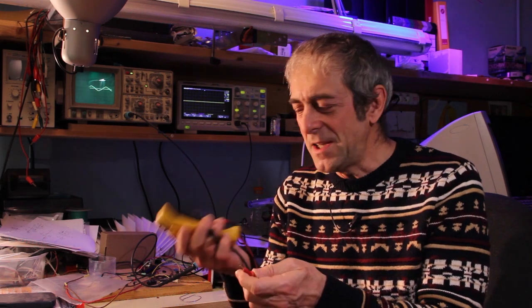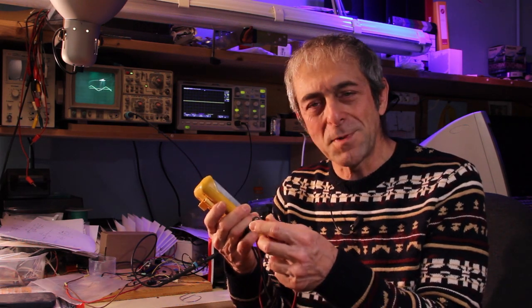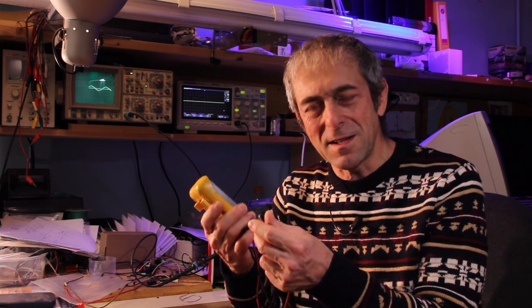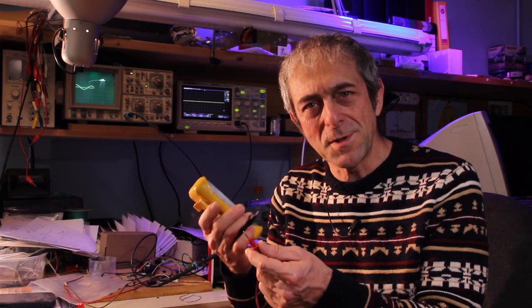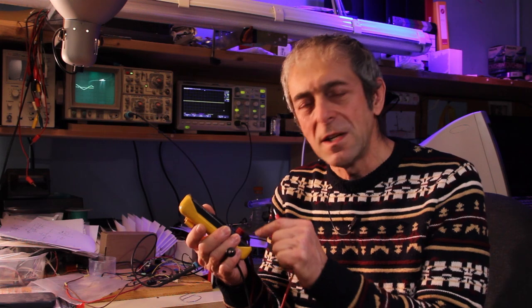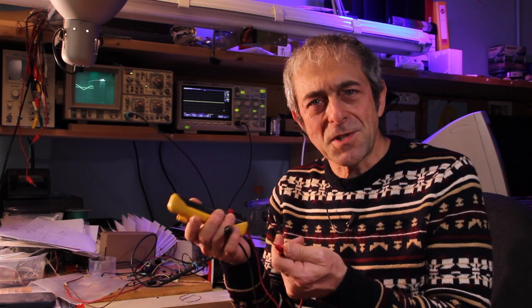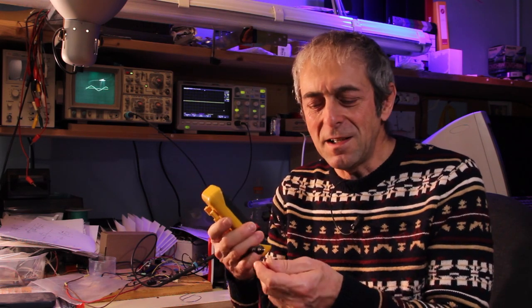Consider that in the continuity test, as you can see here with this instrument, when I touch the probes together we have an immediate feedback of the continuity test with a beep. This is important because when you are doing a continuity test, you need immediate feedback between the moment in which you touch the probes together and the moment in which you get the beep feedback. Otherwise it takes longer than your reaction and it would become useless, and that instrument was like that.